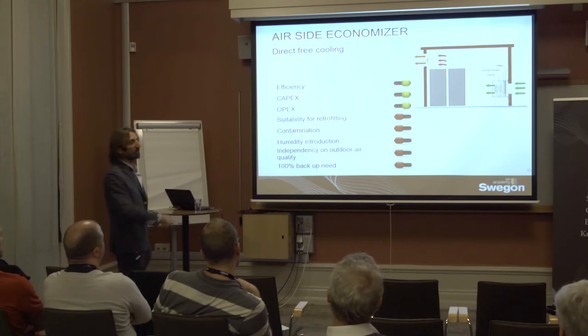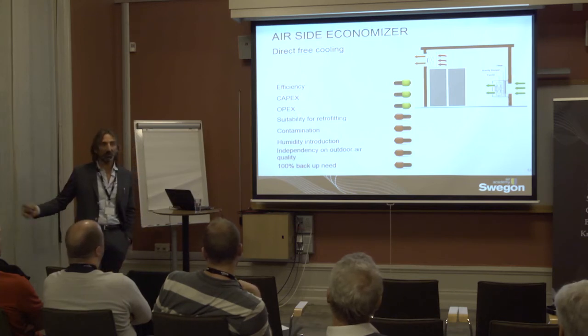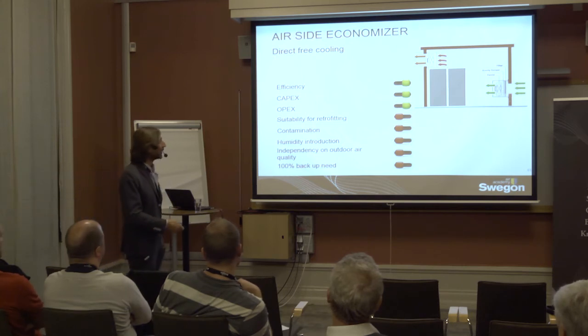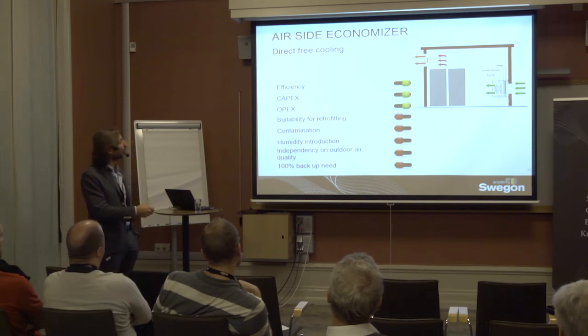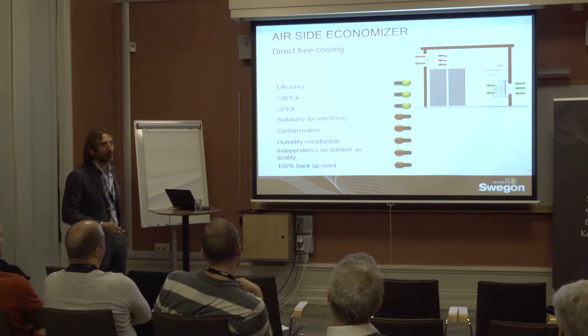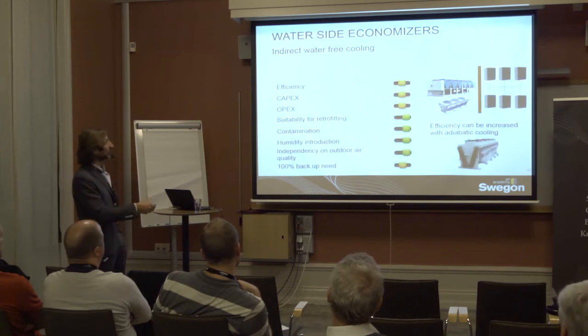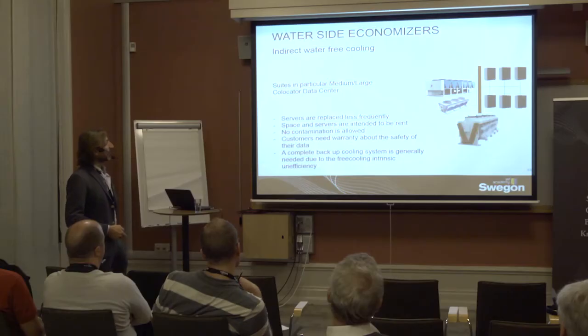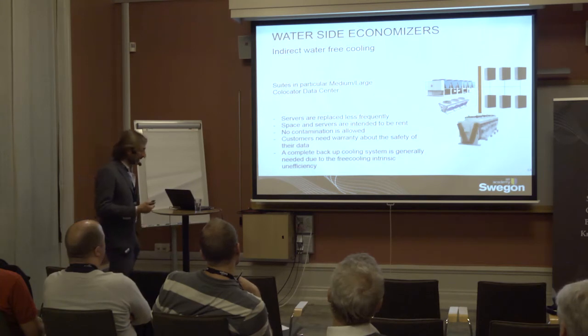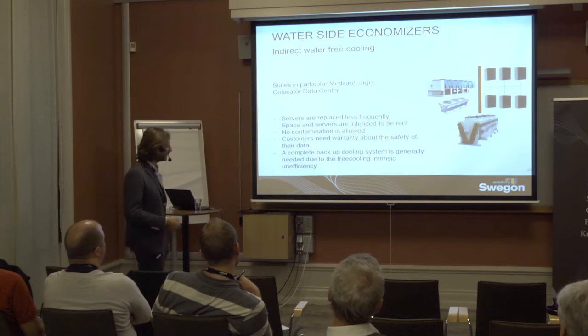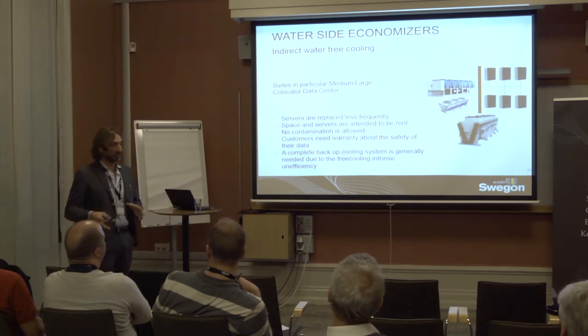And in a system like this one, we have to have 100% mechanical backup cooling, because if during a couple of days during the year we cannot use external air, because of burning outside, for example, or pollutants, we have to be able to cover the total demand of the data center with a mechanical cooling system. So we have to provide 100% backup cooling. In this situation, probably we don't need 100%, but we need a high rate of the total cooling needed to be covered by a mechanical cooling system because of the inefficiency linked to the water free cooling system. And it is mostly used in not hyper, but big data centers, where we need the separation between the indoor and the outdoor.